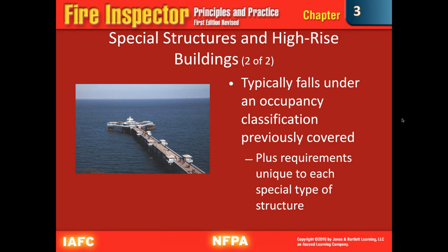Special structures and high-rise buildings. I know you guys don't have any high-rises in your areas, but who knows where your careers are going to take you. High-rise buildings usually have occupied stories 75 feet or more above the lowest level of fire department access to the building. We can't just put a ladder all the way to the top of a high-rise. Special structures include open structures, piers, towers, windowless buildings, underground structures, vehicles, vessels, water-surrounded structures, membrane structures, tents, those kind of things. Those are your special structures.